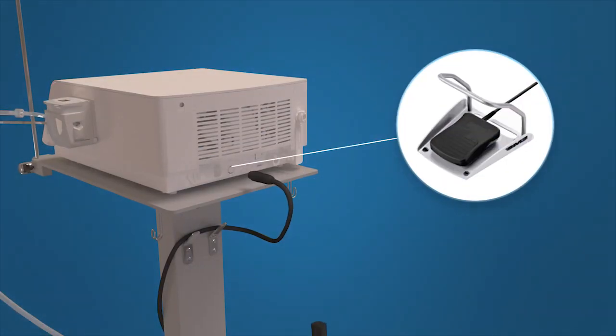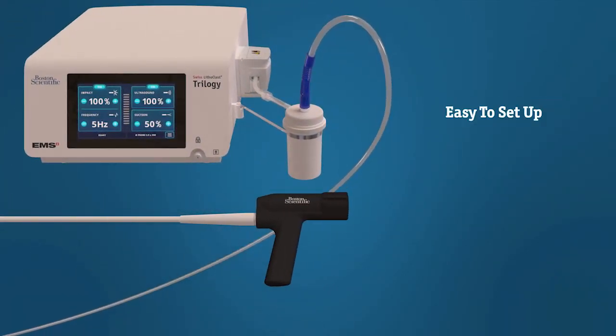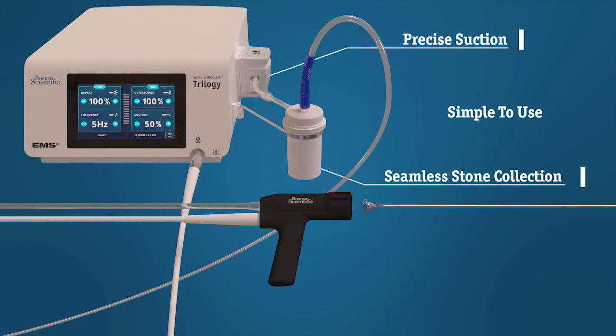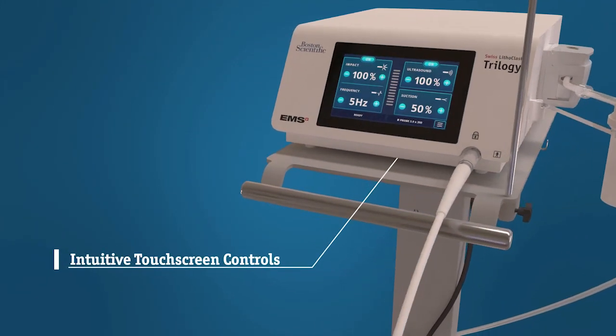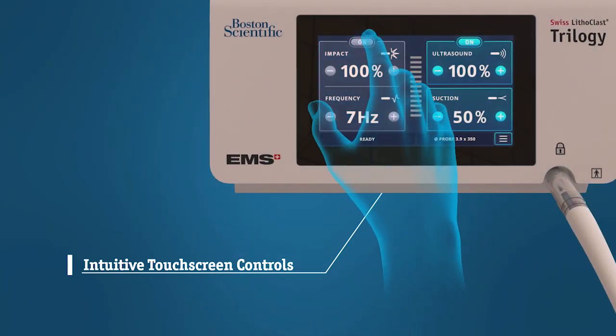The LithoClast Trilogy lithotripter is an integrated plug-and-play system. It's easy to set up in the OR and designed with features to make it simple for the physician and staff to learn and use. Its centralized touch screen facilitates an intuitive user experience, allowing the user to customize energy and suction settings with a simple press of the finger.